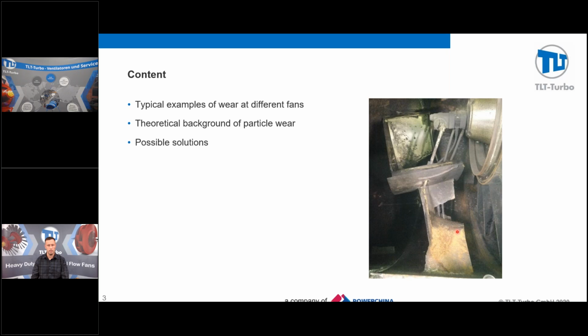So they have rock dust and they have water droplets. They picked up a moisture content at the same time they have a high pH, and it aggressively deteriorated the fan portion itself. Now, these are all things that can be mitigated in the future with different materials now that they know that their mine is producing this kind of environment. But it just gives you a scenario how all things mixed together can really accelerate things. So we'll dive into the first portion of the fans.